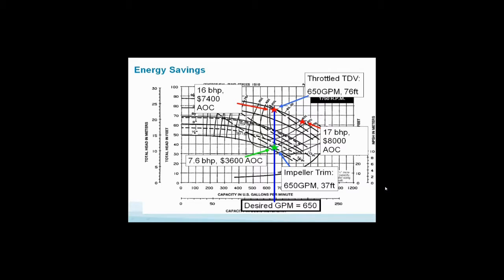A variable speed drive does the same thing as trimming the pump impeller. You just dial the speed down. I've gone from 17 brake horsepower at initial startup to 7.6 brake horsepower. I've cut the operating cost in half. Now do you see why ASHRAE says you got to do this? And now you see the power of the system sizer in helping you do these calculations and making sure things are done right. Based on 24 hours of operating costs at 6 cents a kilowatt hour, you see the savings potential. And now I think you understand why ASHRAE wrote this in the standard and why DOE is saying this is going to become the energy code for every state in the union.